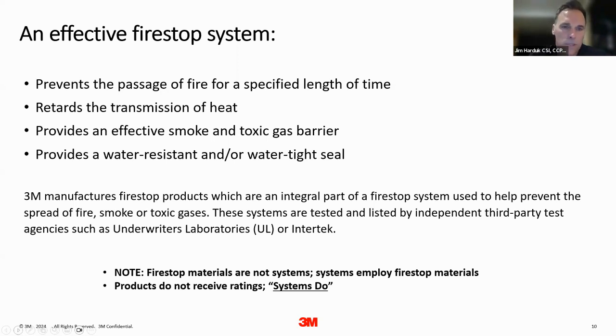And in some situations, the fire stops that we use must also be water resistant or watertight. I'll discuss some of that a little bit later when we get into some of the testing. But basically, 3M manufactures these products, which are integral to Firestop systems. And the materials that we use for fire stopping, obviously, are intended to stop the spread of fire, but they also must seal against smoke and toxic gas. Next slide, please.